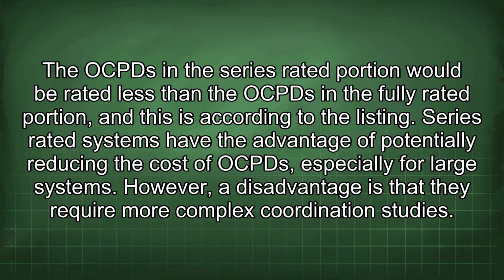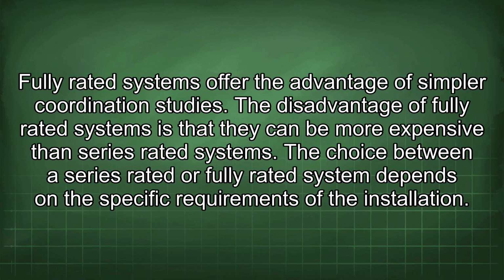Series-rated systems have the advantage of potentially reducing the cost of OCPDs, especially for large systems. However, a disadvantage is that they require more complex coordination studies. Fully rated systems offer the advantage of simpler coordination studies. The disadvantage of fully rated systems is that they can be more expensive than series-rated systems.